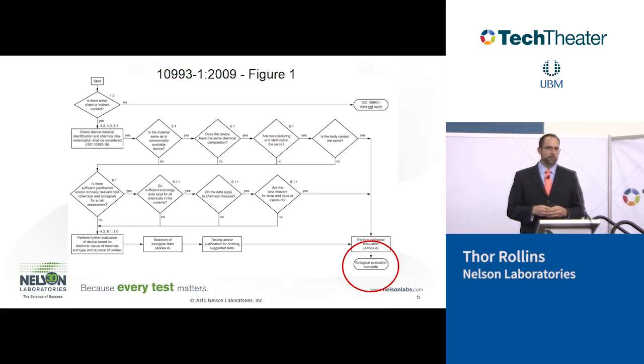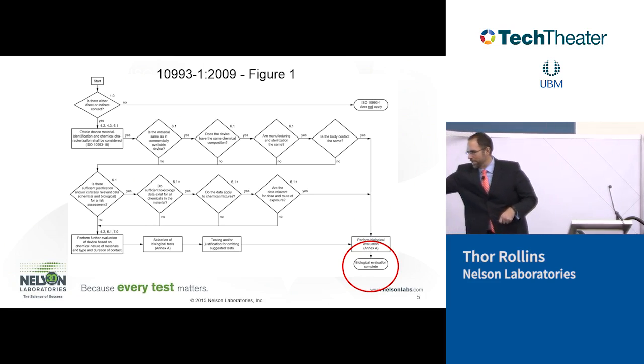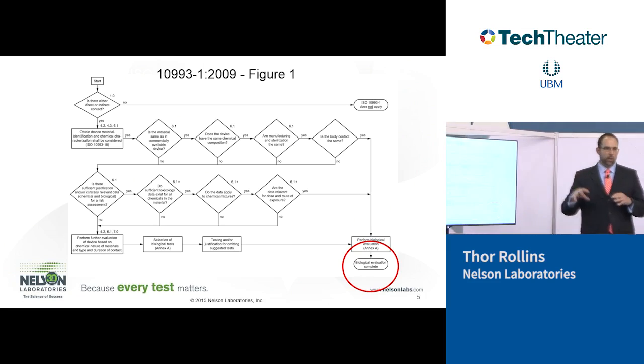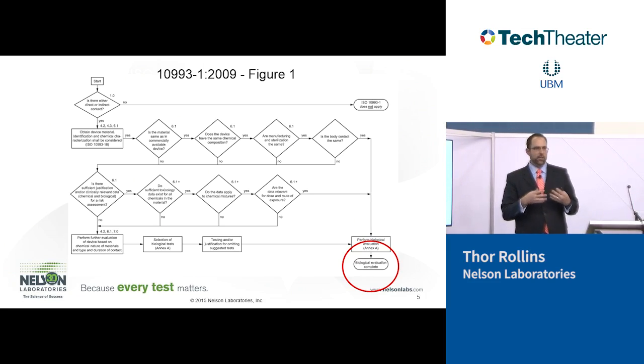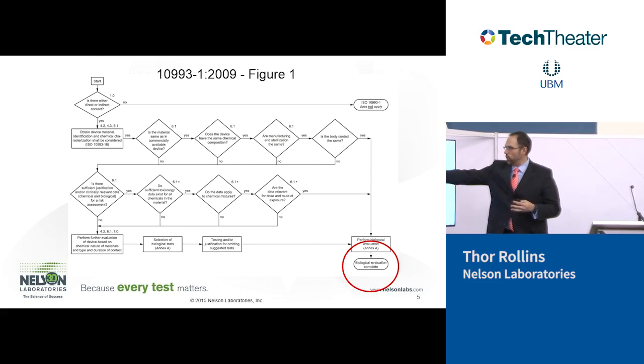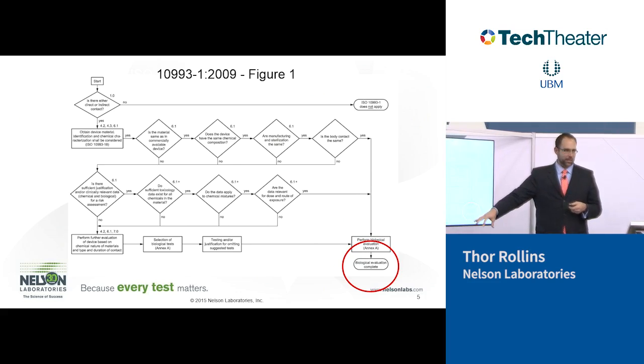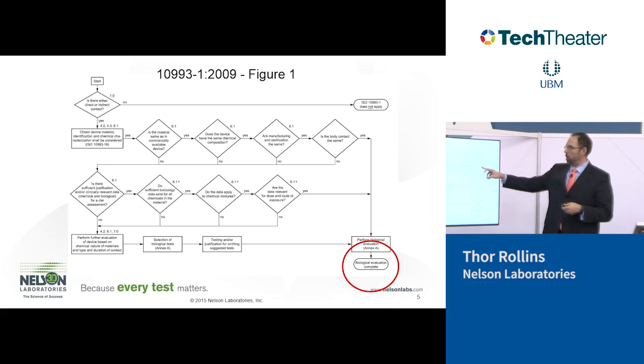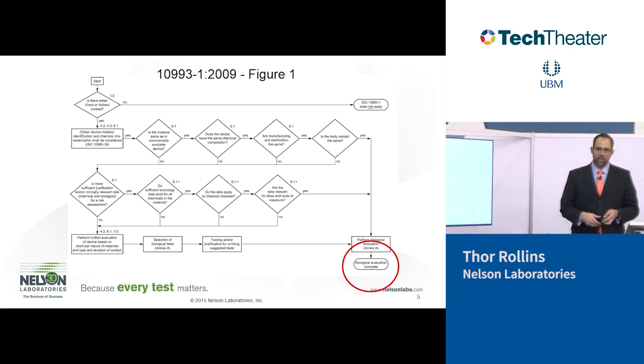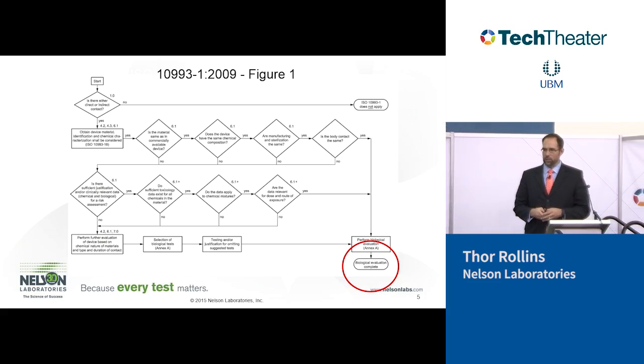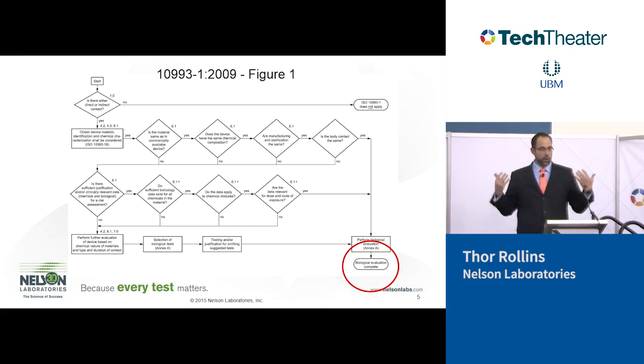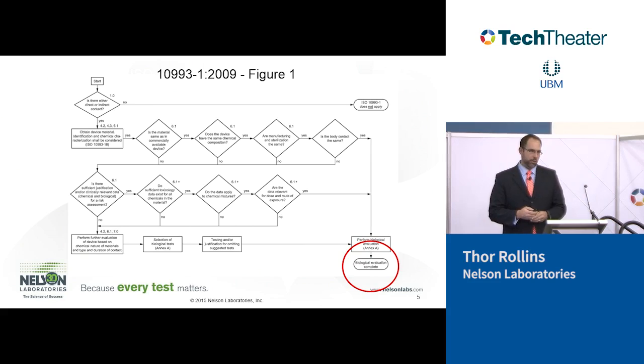Everyone's familiar with this flow chart. This is the flow chart of ISO 10993-1, and it's a decision tool to help evaluate biocompatibility. The same concept holds true for changes. And the reason I wanted to point this flow chart out is I always notice that the only part where it talks about testing is at the very bottom of the flow chart. So many people jump right to just repeating testing or doing testing as the way to evaluate biocompatibility. But the standard actually has us go through so many different options before jumping straight to the testing. And in fact, as you see, there are exit points all along the flow chart that allow us to do an evaluation instead of doing testing. And the same thing holds true for changes. In fact, it's actually easier because most of the time we're not doing a brand new device. We're only evaluating a small impact to an already approved device.